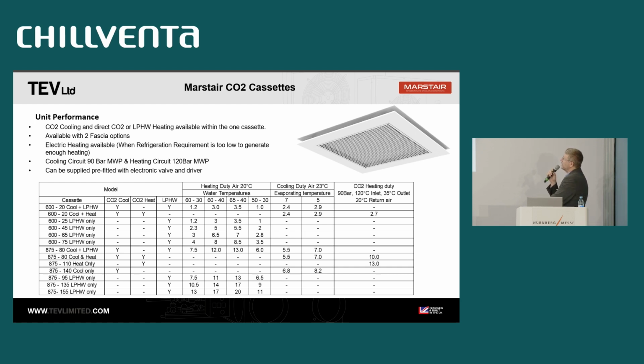We also say on here that we have electric heating as an option, which is quite interesting. You'd say, well, why would you bother with electric heating? Well, it comes back to the subcritical that we were talking about before, where you don't get a lot of heat recovery. In the morning, in a store or something similar, the cabinets are cold, the room's cold, and there's not a lot of cold for refrigeration. You want to heat the space, but there's no refrigeration happening, so there's no heat to recover.